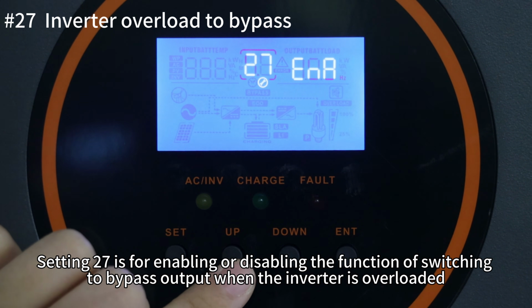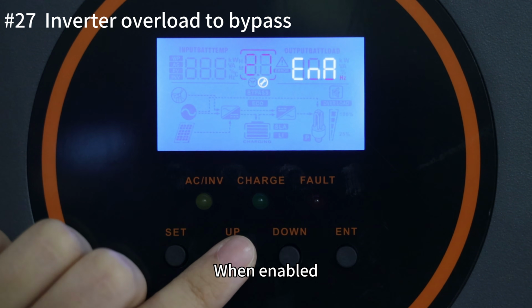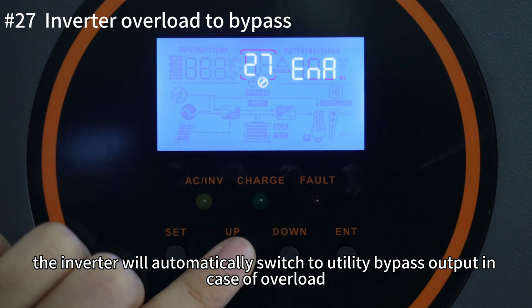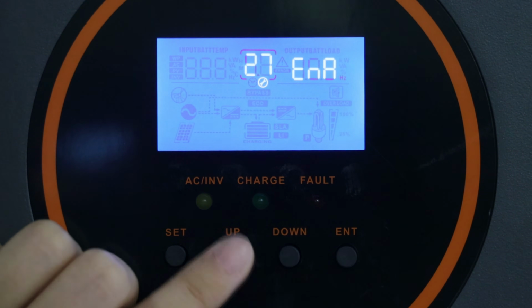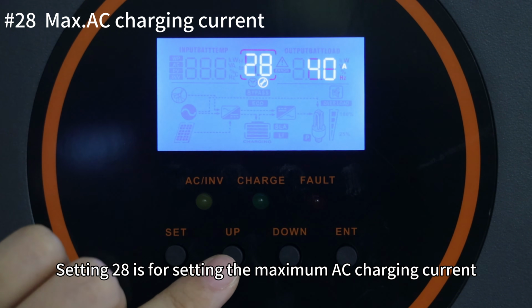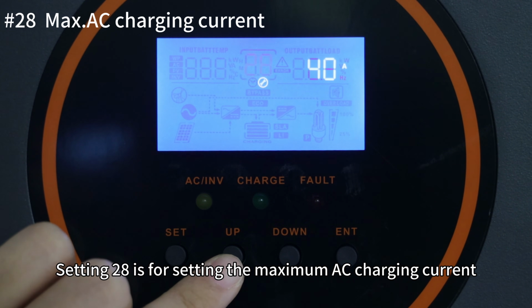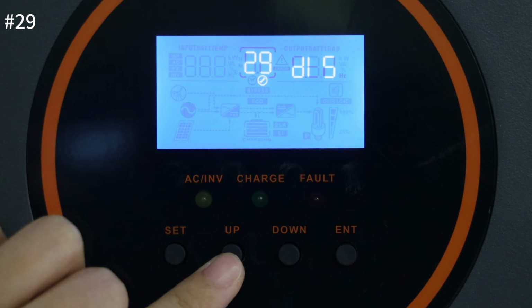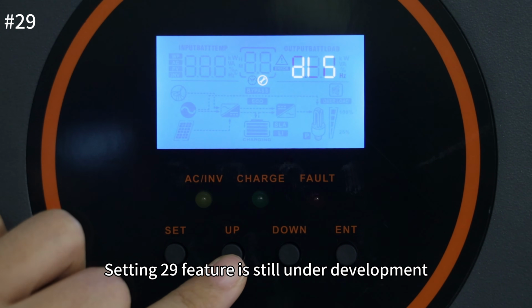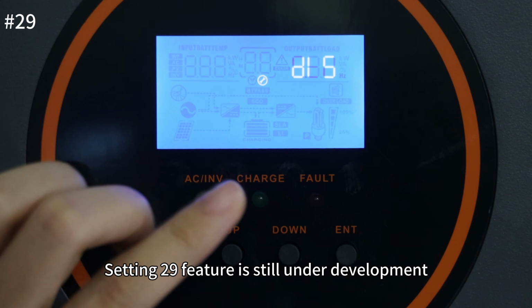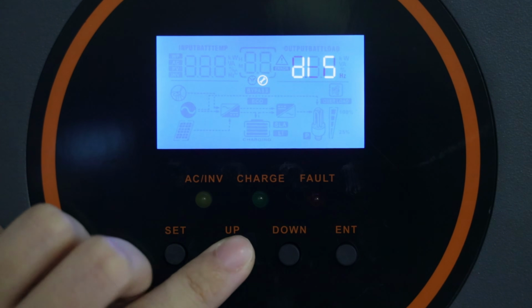Setting 27 is for enabling or disabling the function of switching to bypass output when the inverter is overloaded. When enabled, the inverter will automatically switch to utility bypass output in case of overload. Setting 28 is for setting the maximum AC charging current. Setting 29 feature is still under development, so we skip it here.